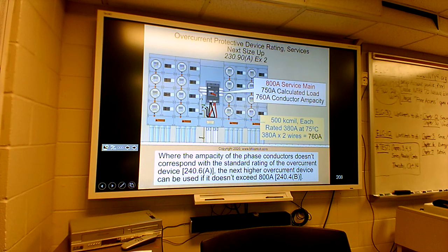So here they've got an 800 amp disconnect, breaker disconnect, a calculated load of 750 amps. And the conductor rating, they're using two 500 kcmil wires rated at 380 apiece, which equals 760. Now here's an exception. The wires combined are rated for 760 amps, but the breaker, the disconnect, is rated for 800, is rated for more than the wire.